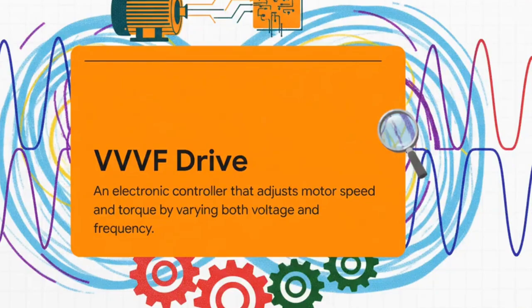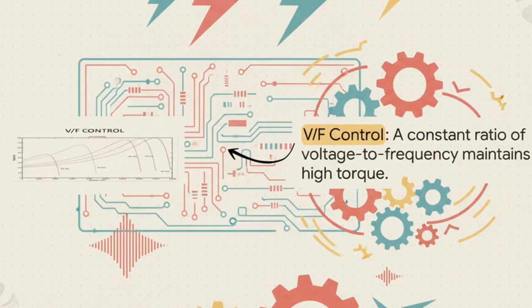That stands for Variable Voltage Variable Frequency Drive. This thing is basically the brain of a modern motor system. Instead of just cranking up the voltage, it precisely controls both the voltage and the frequency of the electricity feeding the motor. It's like having an accelerator and a gearbox with infinite gears. And here's the magic behind it all. The real key is to keep the ratio of voltage to frequency, the V/F ratio, constant. And as you can see from this graph, by doing that, the drive can make the motor produce this high, stable torque across a huge range of speeds. This gives you a level of control that was just impossible with the older methods.